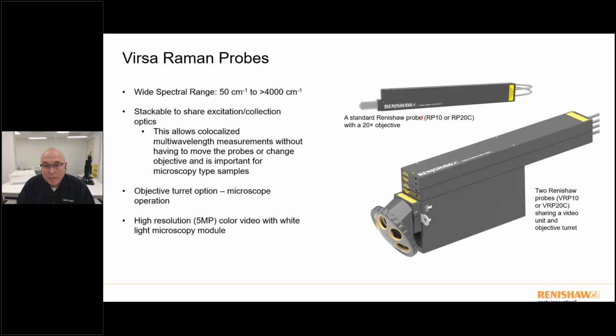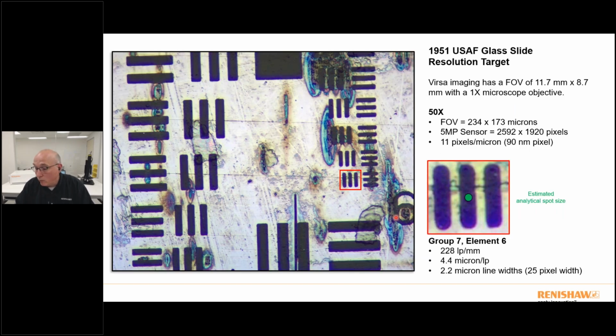So there's quite a lot of functionality with these type of tools. The Virsa probes themselves, amazingly, turn on at 50 wave numbers, so you get close to the laser line performance. And then the total spectral range is really dependent on the laser and the detector limits, but generally the filters will perform to better than 4,000 wave numbers. And they are stackable. So if you have multiple probes, you can stack them, and that allows you to share excitation optics. So you can have completely automatic laser selection in the software without having to physically change anything on the instrument. And that I feel is really unique. Like I said, you can have the objective turret in here, and then on the box itself, we have a 5 megapixel video camera with white light microscopy on there. And that actually does a really, really good job at being able to visualize the sample.